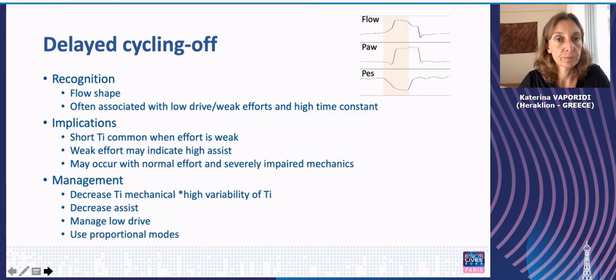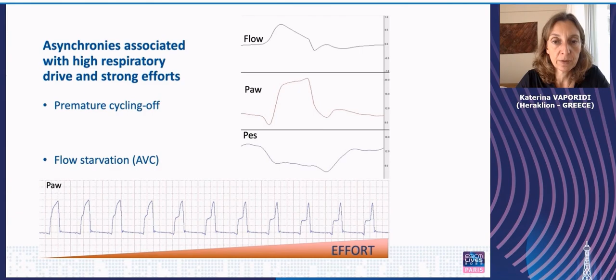Another way to classify asynchronies is to focus on the context where they occur. So we have asynchronies associated with high respiratory drive and strong effort, such as premature cycling off that we saw before. And in assist control mode, assist volume control mode, the phenomenon called flow starvation. As on the panel below, on the bottom, notice the change of the airway pressure waveform with increasing patient effort. This can be managed with an increase in inspiratory flow or using a decelerating form of inspiratory flow.